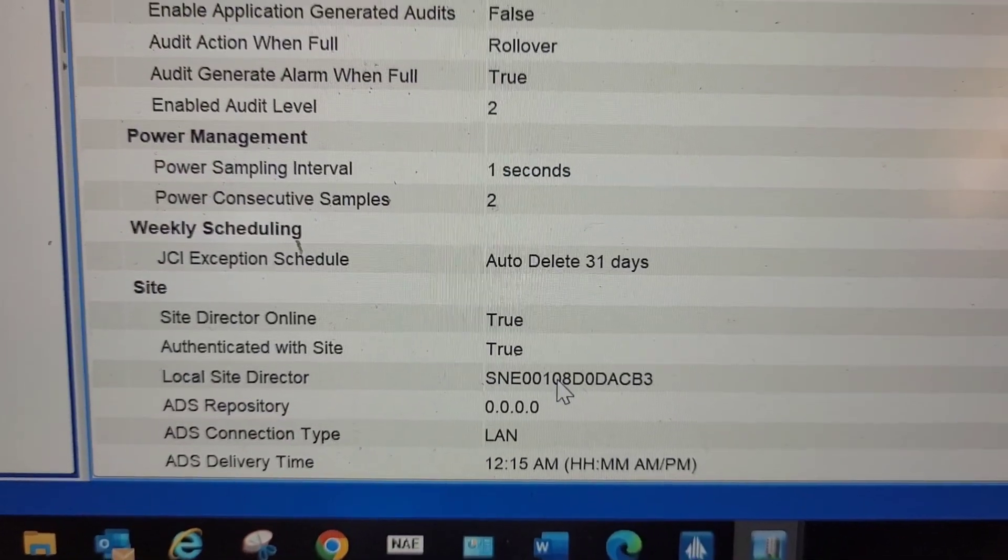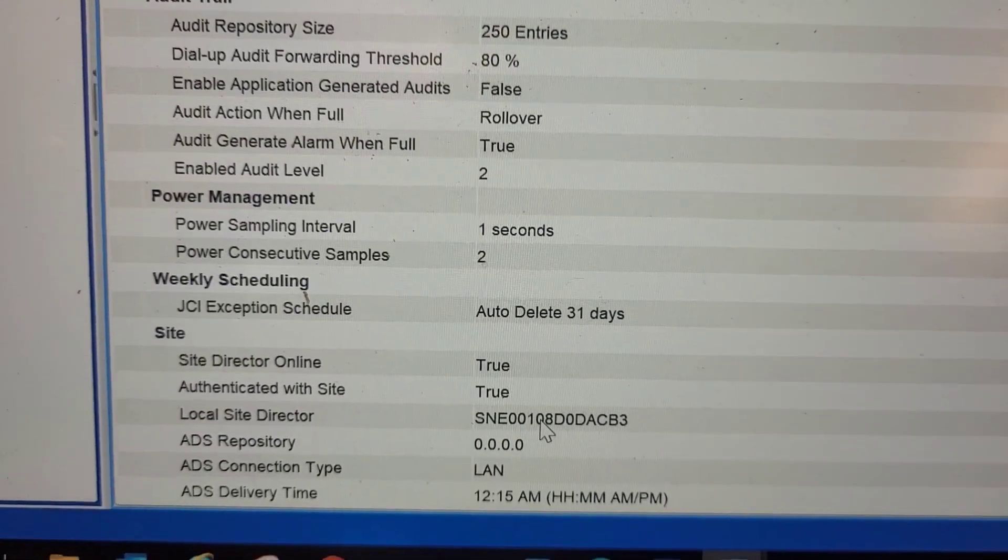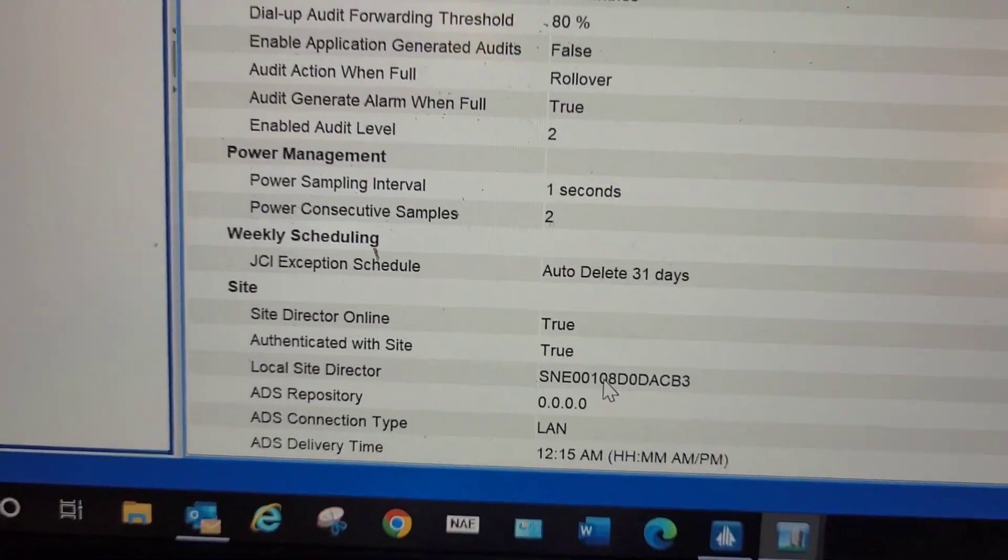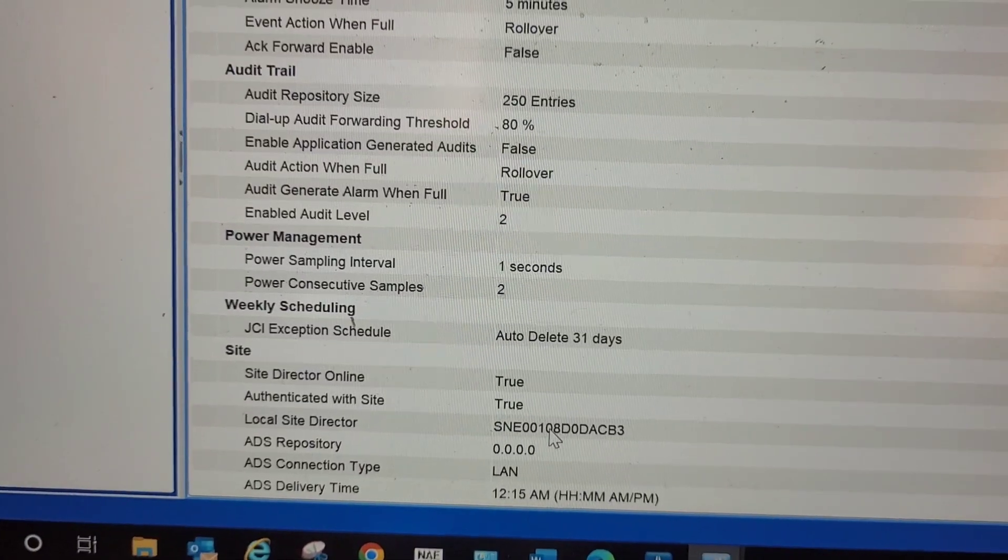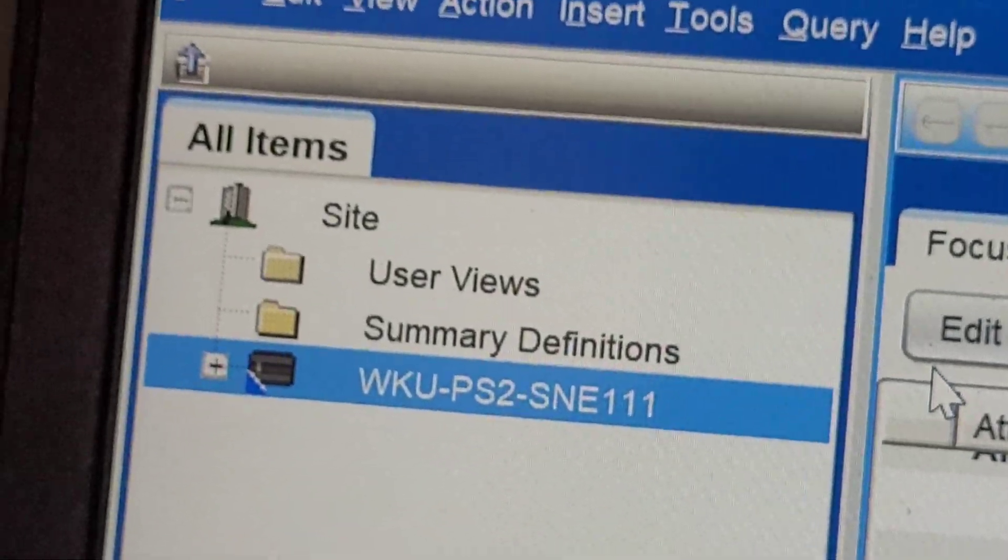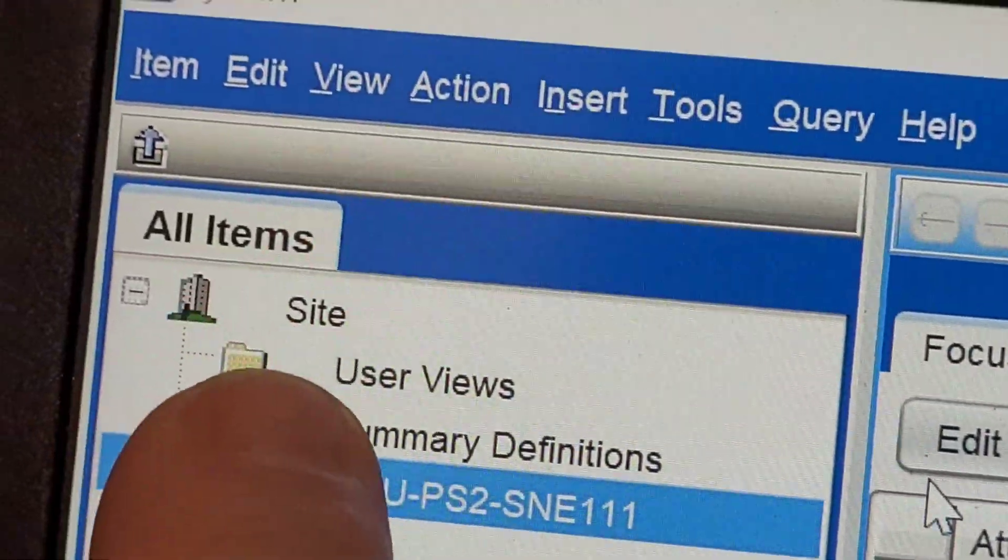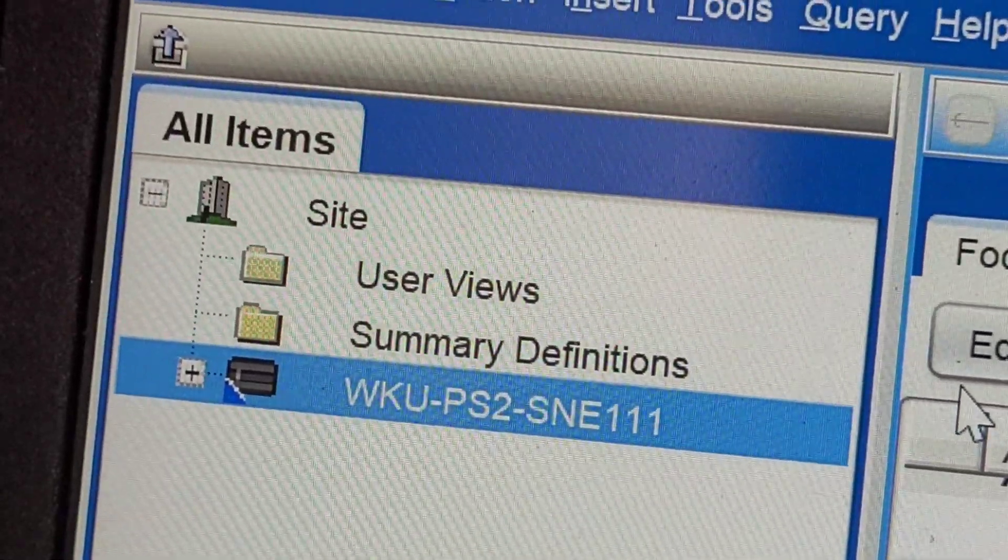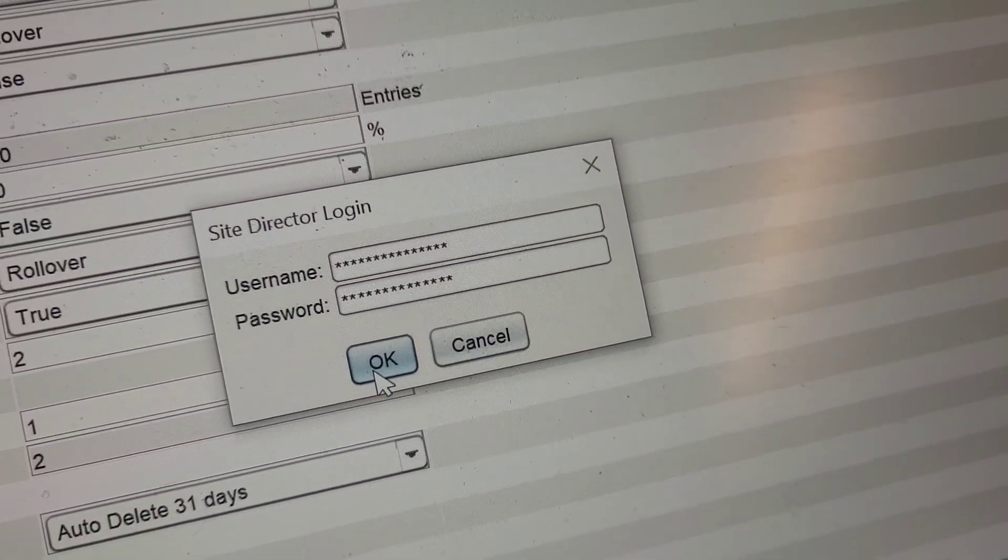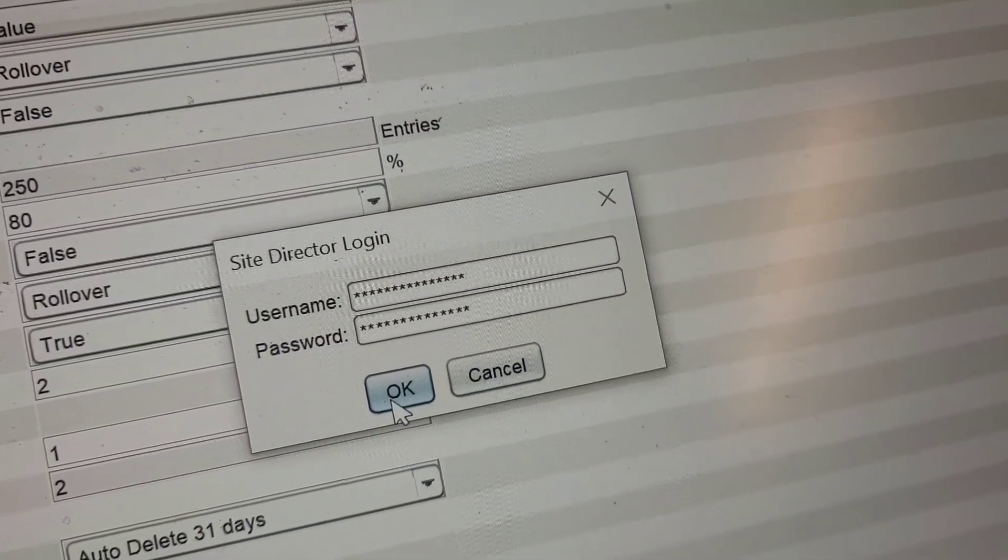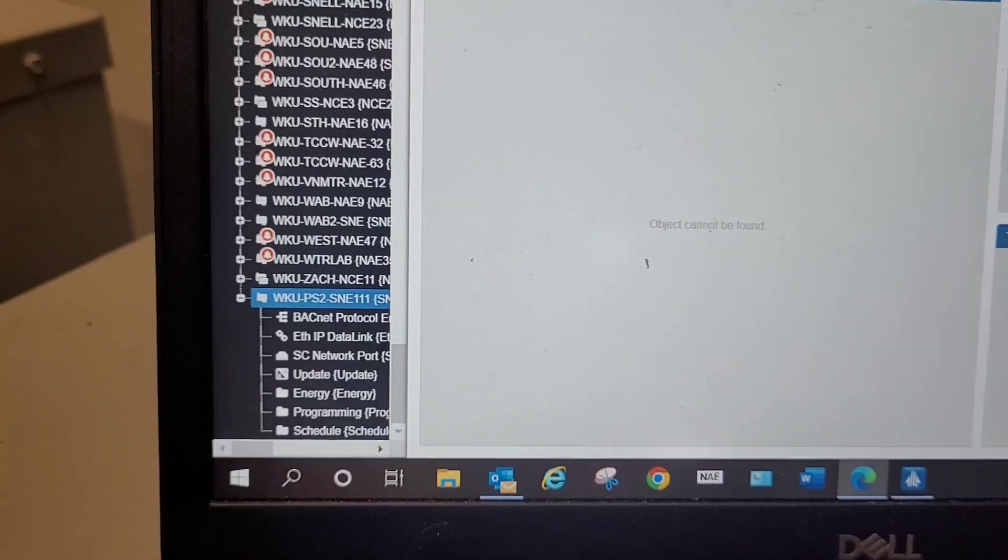This is where I would enter the IP address for my server. And then once you do that, it is going to ask you to enter the login credentials so the device can log into the server. That's part of the security feature with some of these newer models with the SNEs. So that's what we're going to do now to where we can pair it with the server and then begin building the rest of the system out and pulling our meter into the system. When you go to pair the server, you enter the IP address for your server. This is the window that's going to pop up asking for the login information to your server. Once you enter that information and press OK, the SNE will reboot.